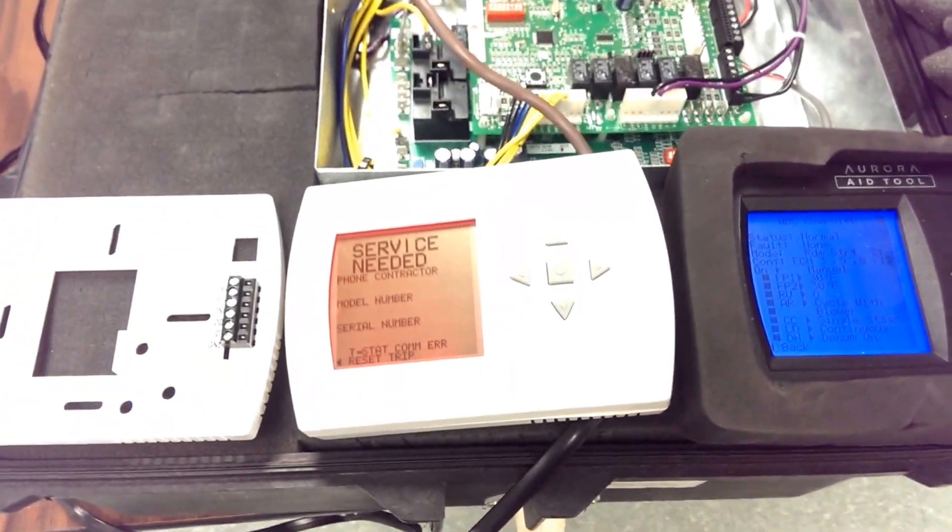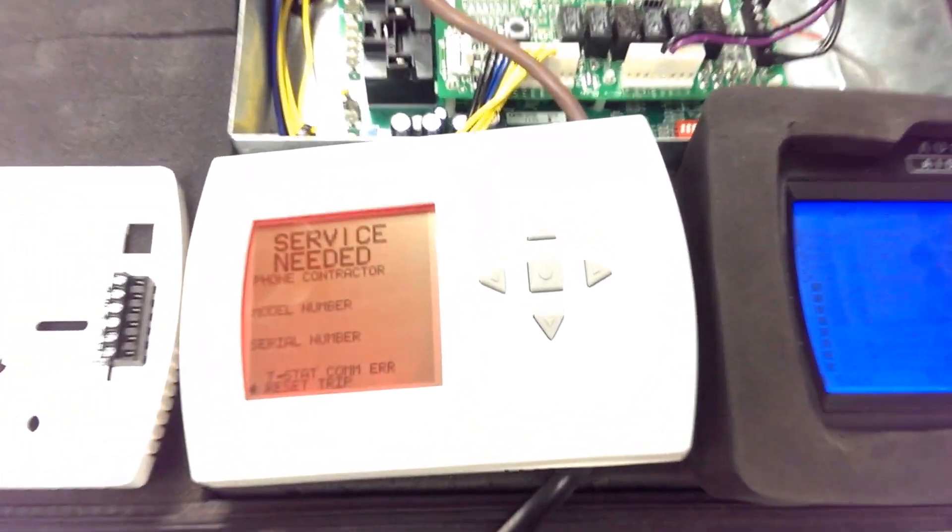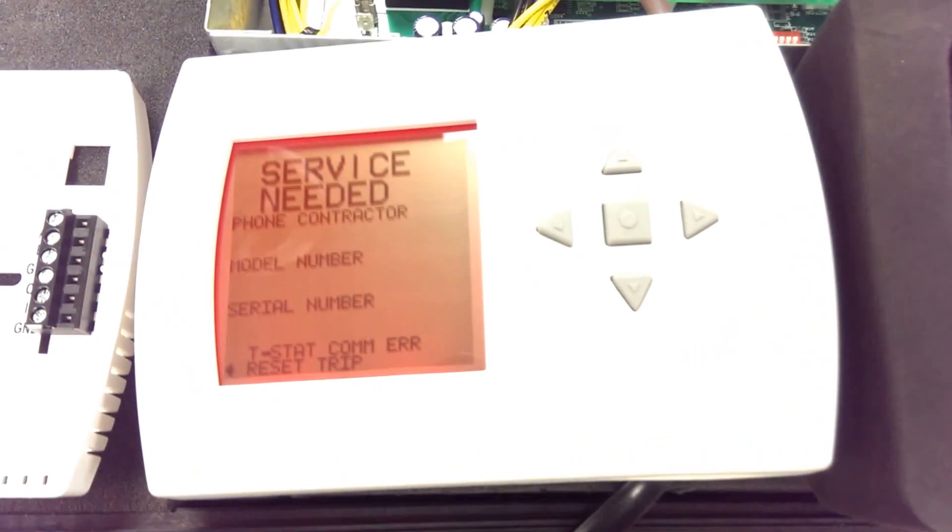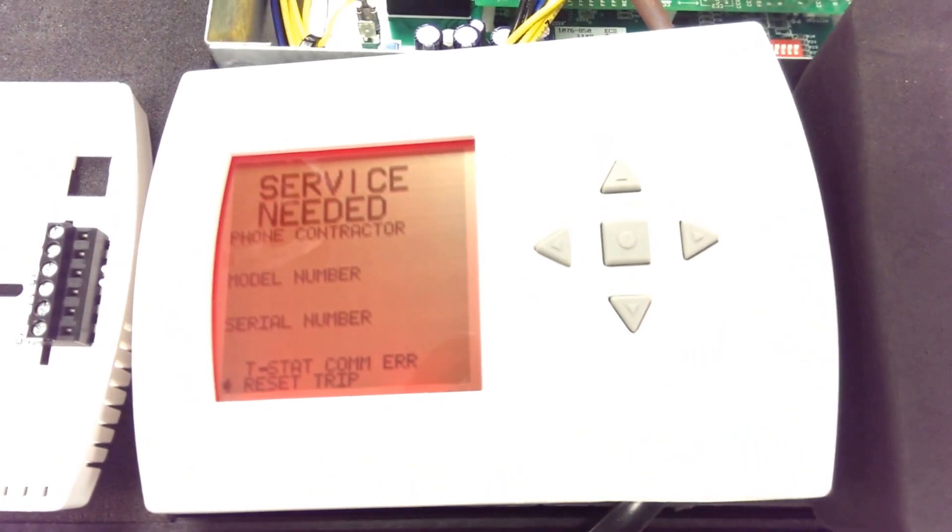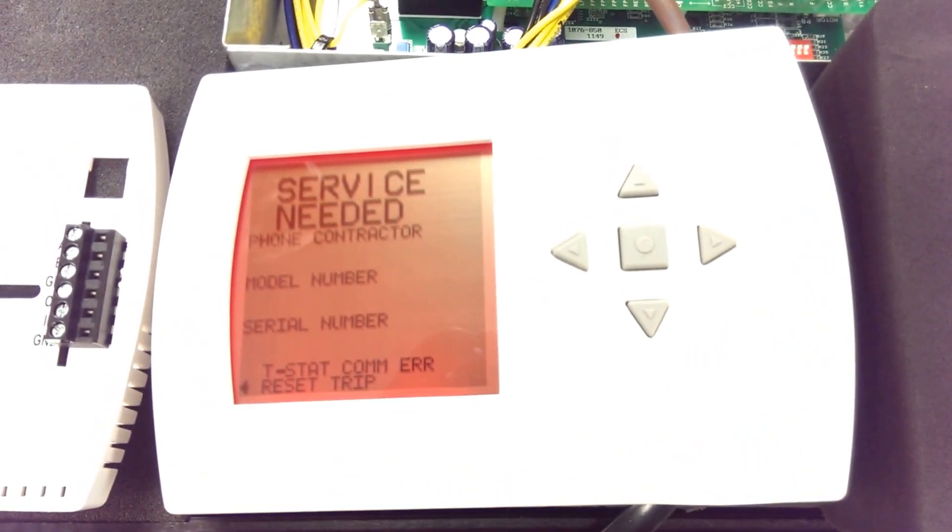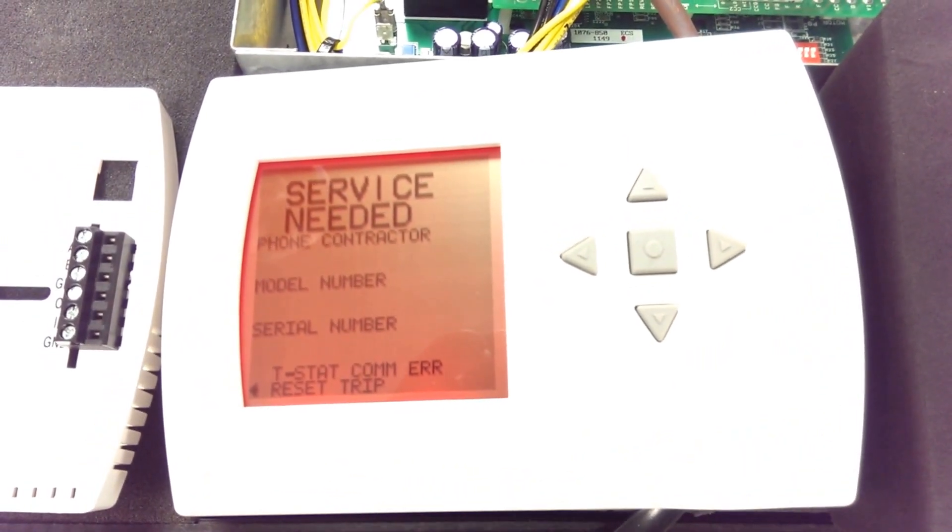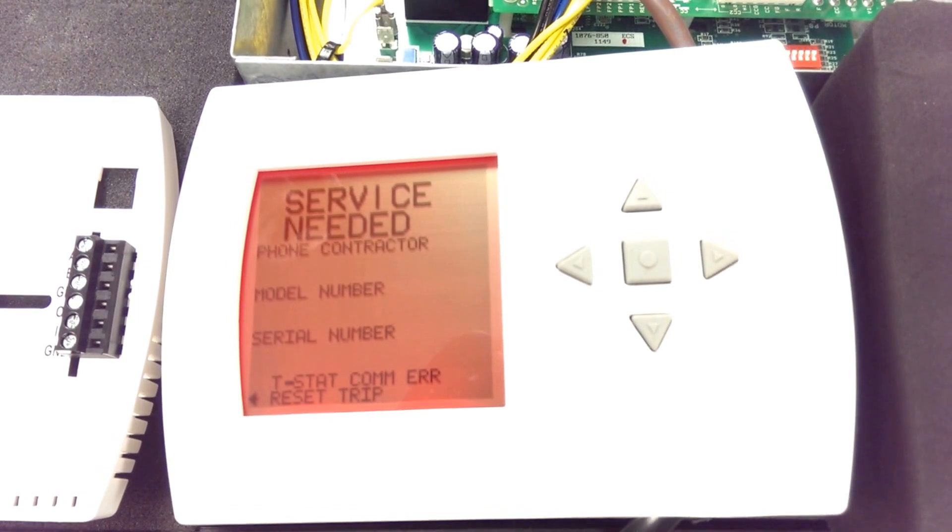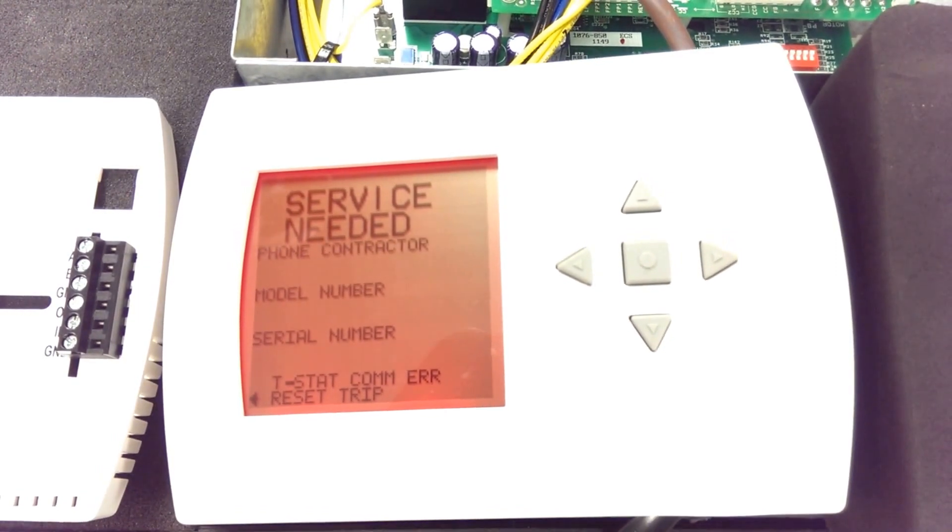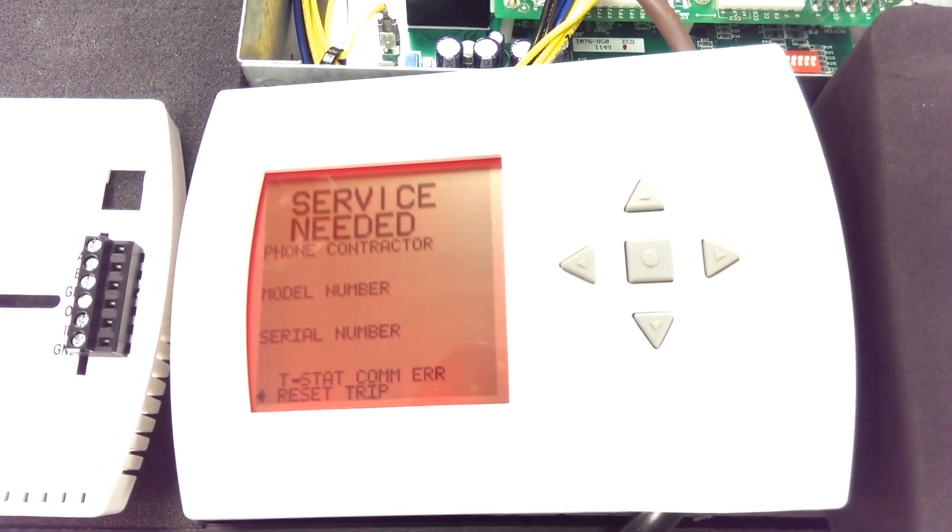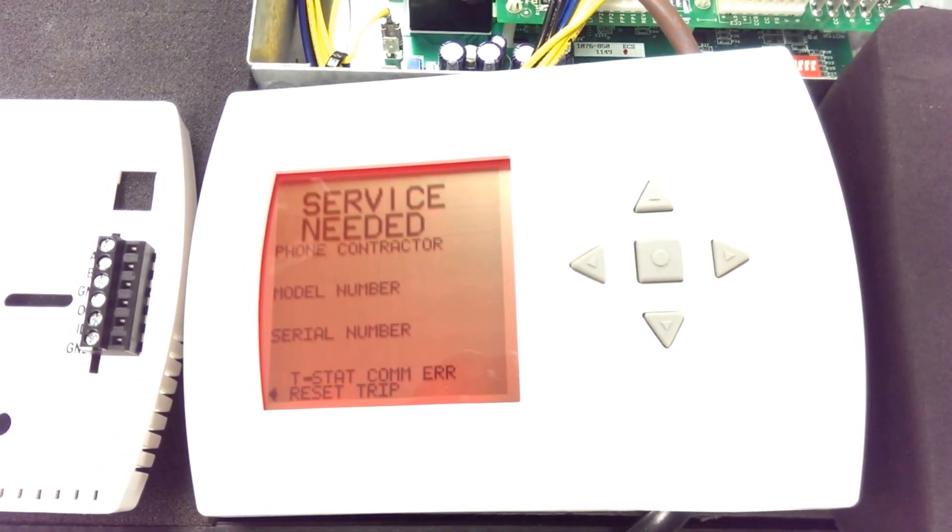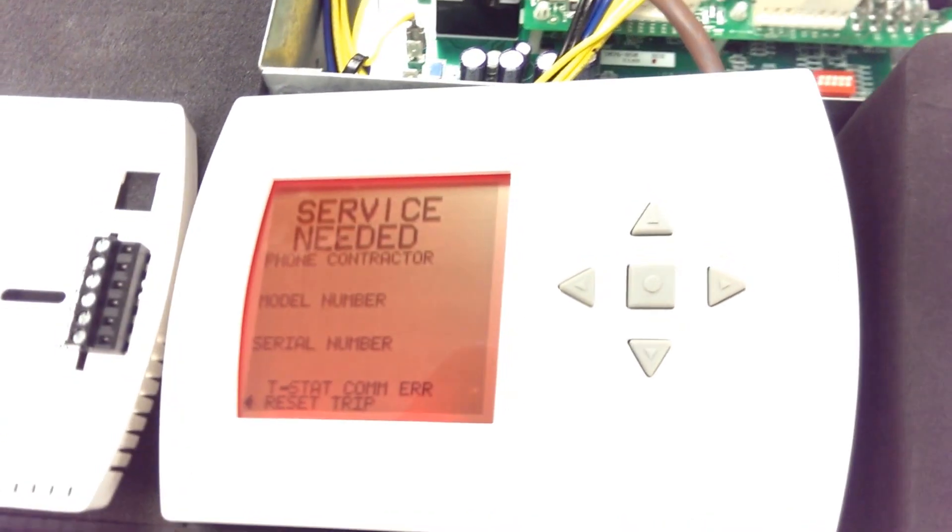If we look at the thermostat itself, we can see that we actually have an error on the thermostat. It says we have a T-stat communication error. The reason for that is the thermostat has not been added to the Aurora board.